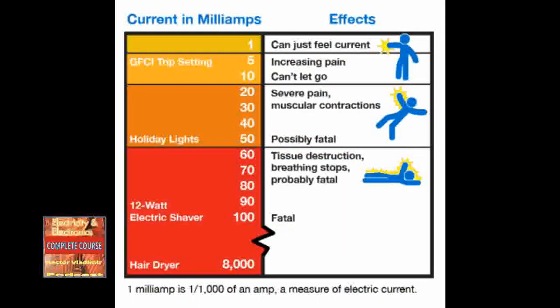Electric shock levels are rated by value of current flow and their effect on the human body. Current of 1 mA is barely noticeable. Current of 5 mA is the highest harmless value but can be painful. From 10 to 20 mA, there can be sustained muscle contraction — the victim cannot let go. From 100 to 300 mA, paralysis of respiratory muscles can be fatal, with severe internal and external burns and organ damage. 2 A can cause cardiac arrest and is most times fatal.